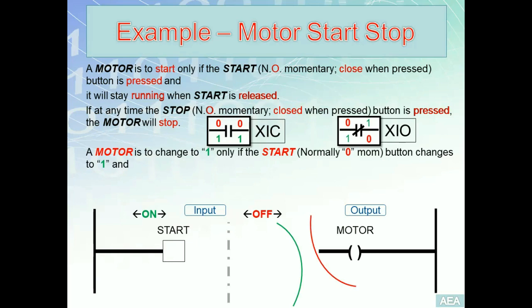The XIC (examine if closed) instruction is used when you want the output state to follow the input state — use XIC to energize an output when the input changes to one, or to de-energize an output when the input changes to zero. On the other hand, use XIO for an inverse relationship: use XIO to energize an output when the input changes to zero (open state), or to de-energize an output when the input goes to the closed state (one).